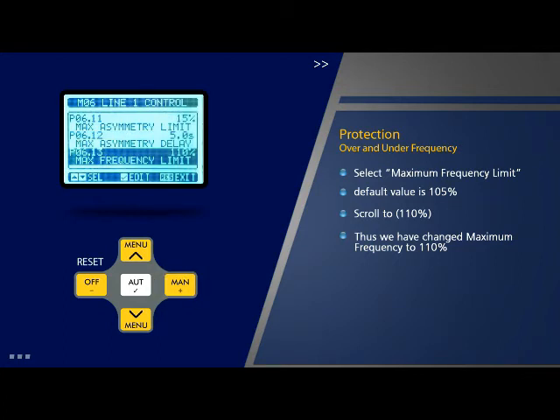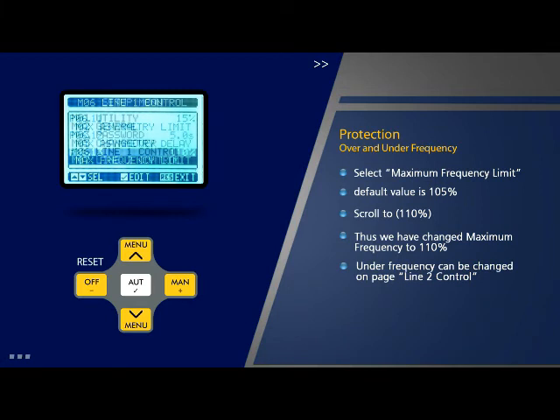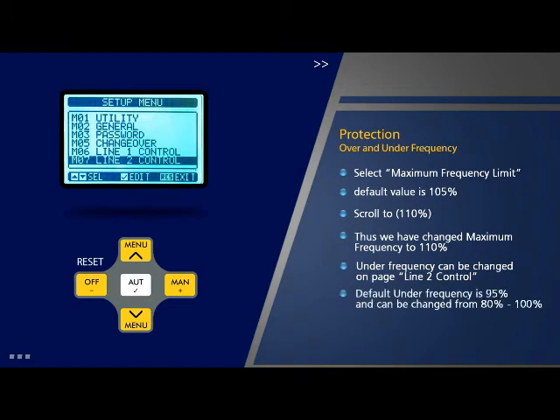Similarly, the set value for under frequency can be changed using the parameters on the line 1 control page. The default value for this parameter is 95% and can be changed in the range of 80% to 100%. On similar lines, the set values for over and under frequency for line 2 can be changed by selecting the respective parameters on the page 'Line 2 Control'.